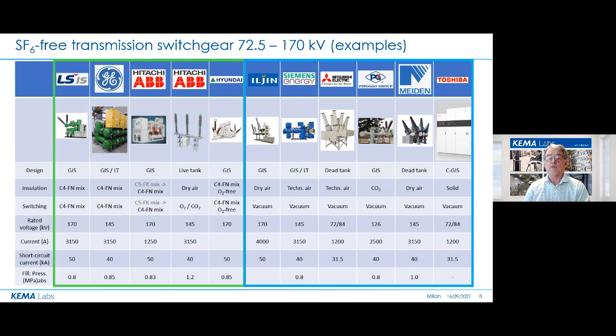The second group, in the blue square, uses vacuum interrupters for interruption and different types of compressed natural gases, which can be dry air, synthetic air, or technical air, and even CO2 for insulation. Regarding ratings, the two technologies have been claimed to pass tests at the same level, which is in the 145, 170 kV, 50 kA range. An interesting development is the technology sharing between different companies.